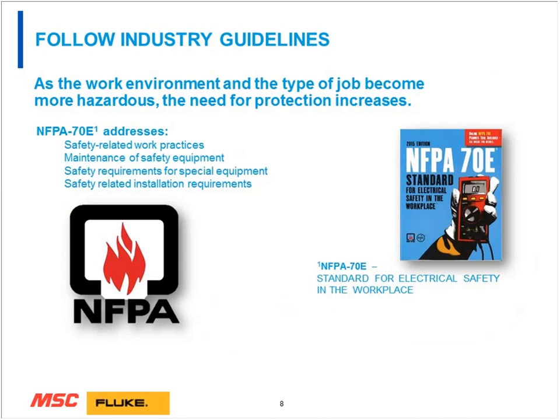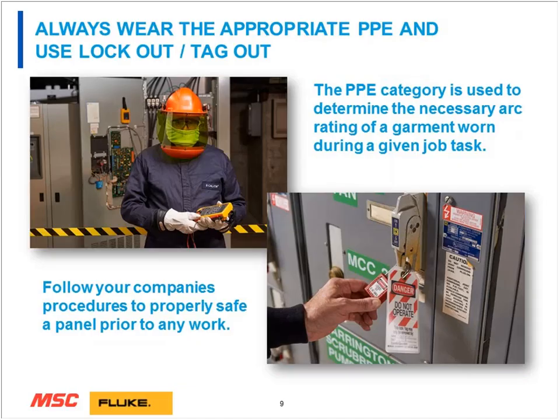You need to follow industry guidelines. Now, NFPA, National Fire Protection Association 70E, is the actual standard that you do need to follow, and you should be very aware of this. This works alongside and parallel to OSHA, but this deals with electrical measurement safety. And not just electrical measurement safety, but how we work in a safe way in an electrically charged environment. Now, this standard is renewed every couple of years. This presentation is dealing with the 2015 standard. There's a new one that we're just addressing now. But understand that you should always be aware of your company's industry guidelines when working under these active conditions.